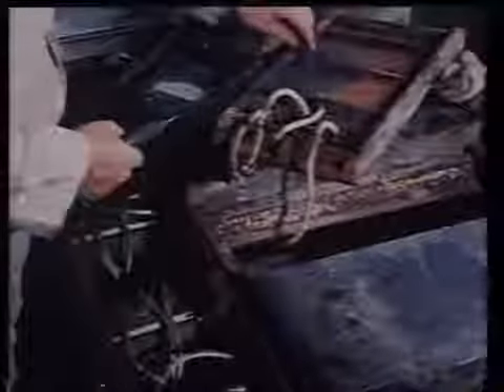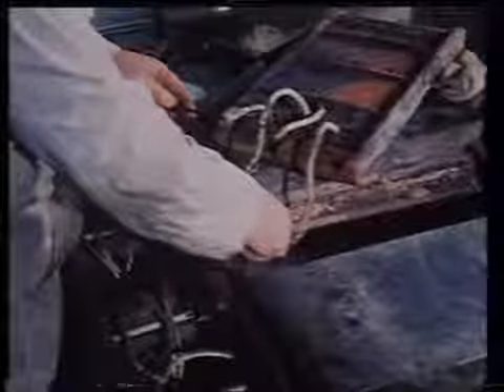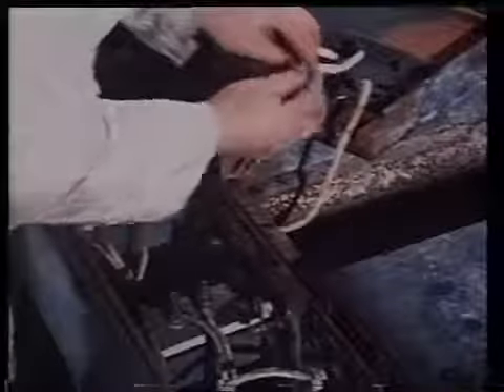Here, a baking oven is checked. Its heating elements are checked to earth and for insulation between each element. Now a heating element in a galley range is checked. Again, the terminals are proved dead, then they're cleaned, where there is rust, dust and grease to clear. The heating element is checked for earth fault as well as for continuity. New heating elements usually have very low insulation resistance readings until they've been heated over 360 degrees Fahrenheit. If the tests are satisfactory, check the heat-resistant insulating beads on the flexible cables. If any are damaged, replace them.